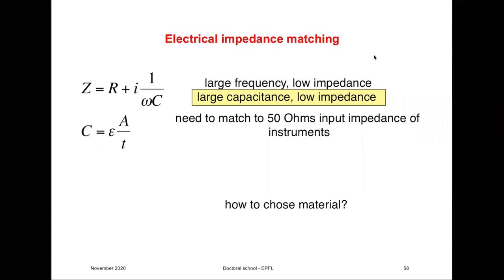We continue our discussion on piezoelectric transducers, and after showing the importance of acoustic impedance matching between the transducer and the object that is investigated, we will now make a few comments about the importance of electrical impedance matching between the acoustic transducer and the instruments that are connected to it to process the signal. So the impedance is given with this relationship here in general, and we see that in the reactance we have a frequency and capacitance.